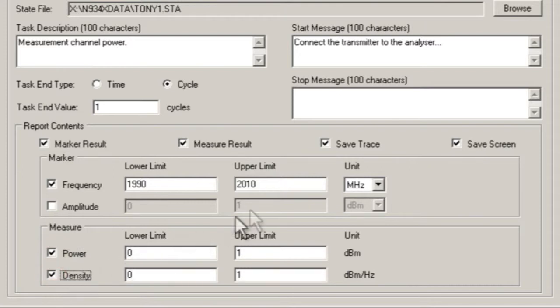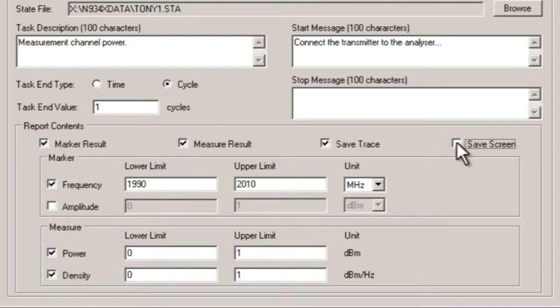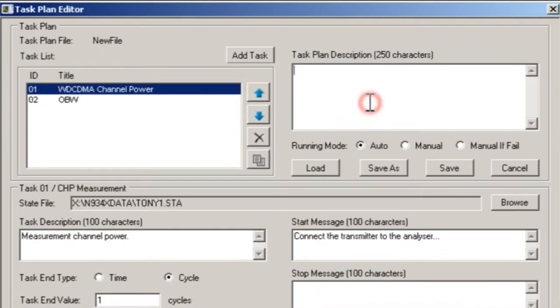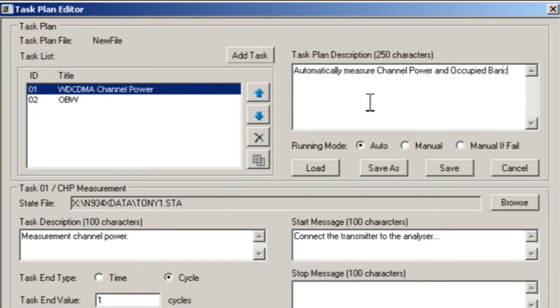And we can even tell the task planner to save the screen image or the trace values as part of the test sequence. We can tell the task planner how we want the operator to step through each of the tests, automatically or manually.